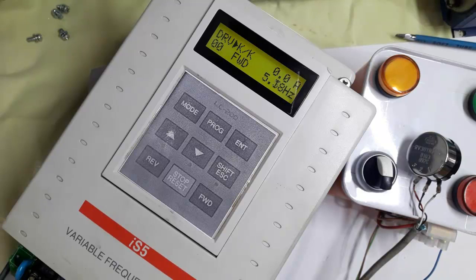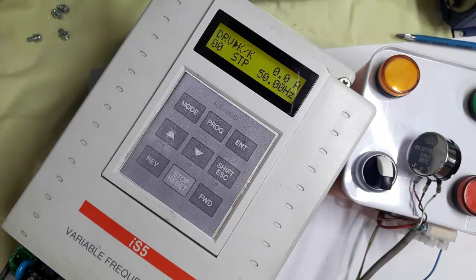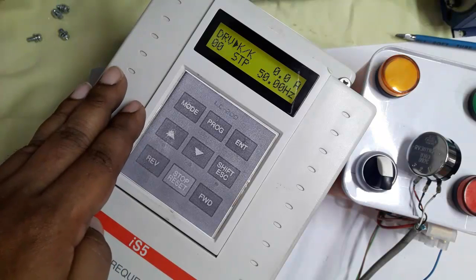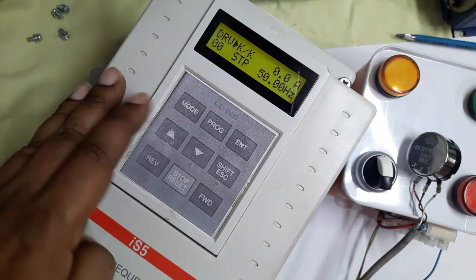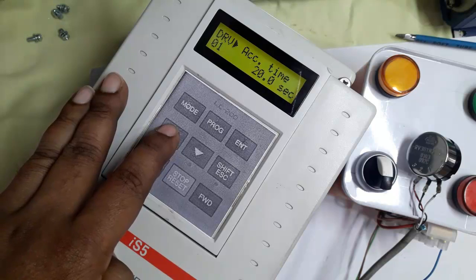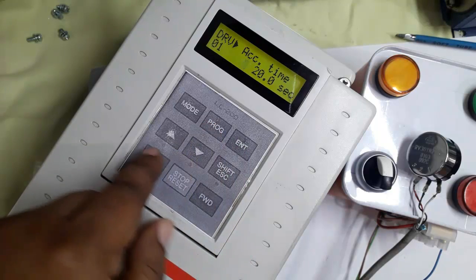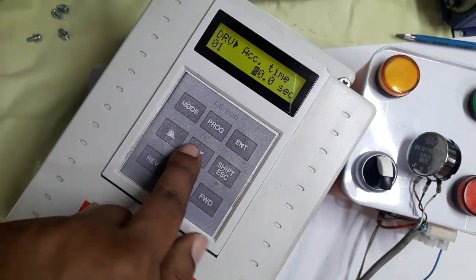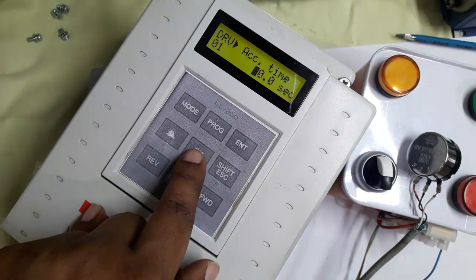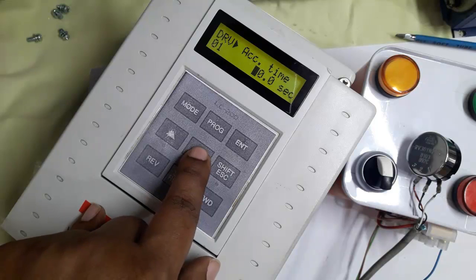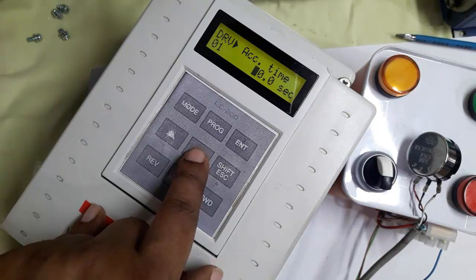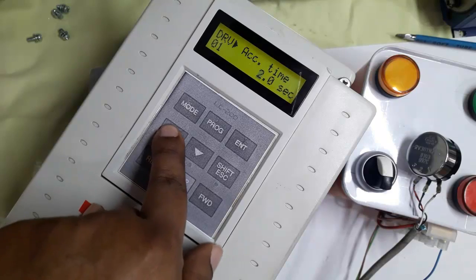In LS iS5 inverter we can run by keypad in any machine as practical requirement or machine requirement. So now we want to reduce acceleration time set in parameter. Acceleration time here are 20 second, we set here 5 second because of run command in full speed. Going to full speed take only 5 second, that's mean speed going to faster from before.